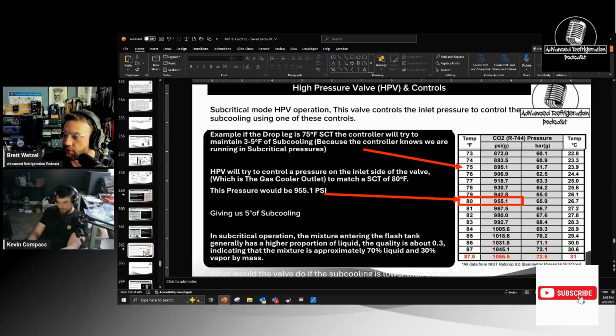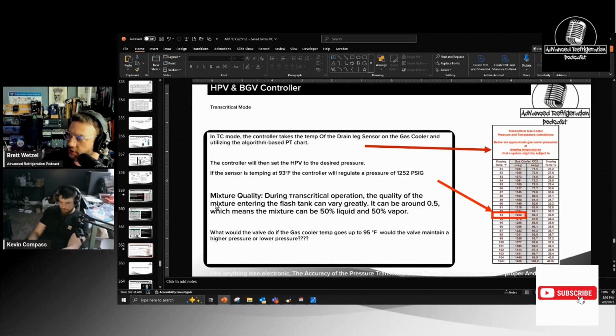Now, what Kevin's referring to on a real hot day, essentially what's going to happen is it uses an algorithmic PT chart. It's just a chart that I think they were just throwing arrows at something and were like, that sounds good. But essentially how this works is when we're running transcritically, it takes that same outlet gas cooler temperature sensor and says, okay, we're running 93 degrees, I want you to maintain 1,252 PSI. So exactly what he just said, if this thing's sitting in the sun outside the rack and the sun's beating down on it and it already thinks that it's 104 degrees, it's going to try to maintain the inlet of that HPV at 1,449 pounds. If it keeps trying to do that and keeps kicking on the compressors instantly, there's a high probability that it'll keep perpetually going off on high pressure.